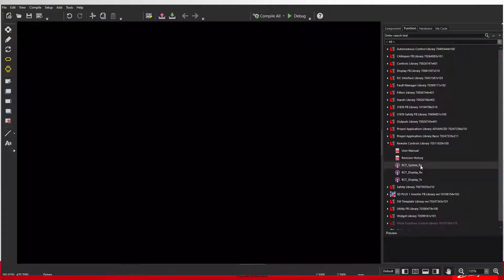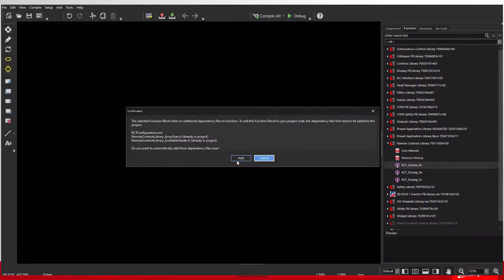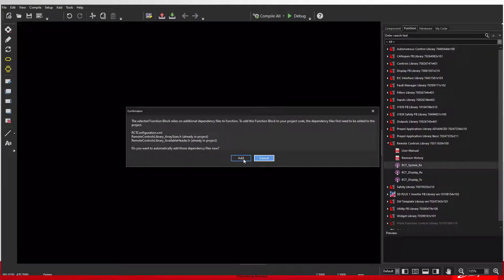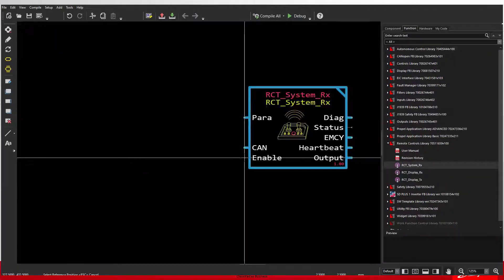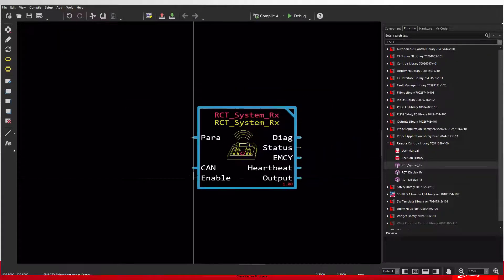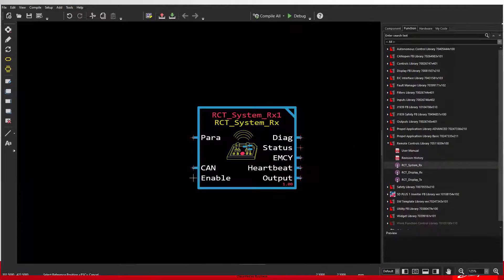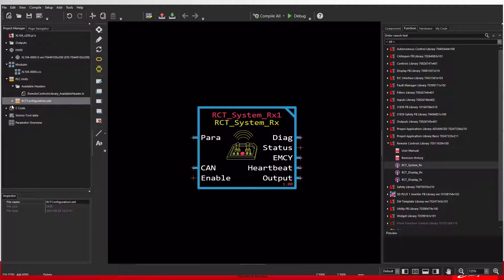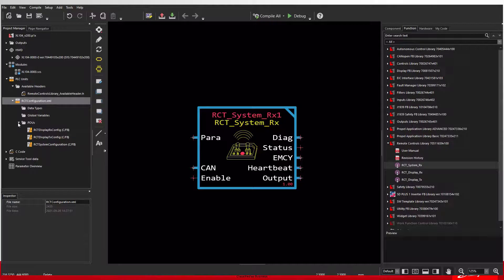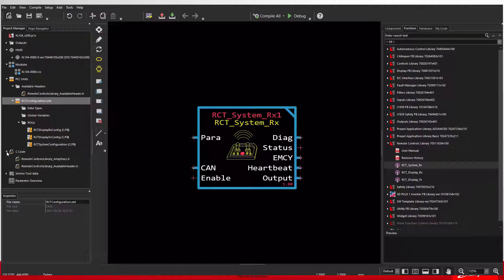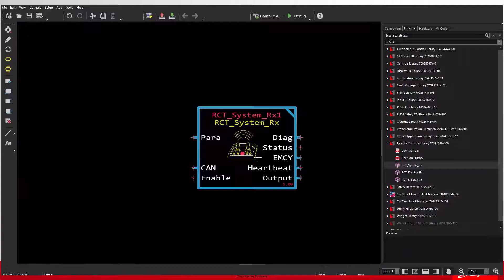When you drag a block into an application in GUIDE, there will be a confirmation that pops up asking if you want to add the default dependency files to your project. It is recommended to add these files and then replace them with the configuration file you received from Danfoss. The configuration file will create the POUs that drive the inputs and outputs for the block.